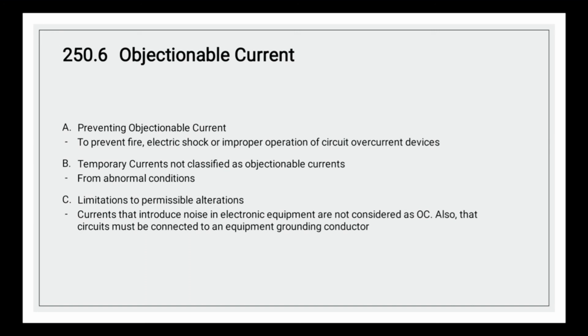Okay, why is temporary current not classified as objectionable current? Because these temporary currents come from abnormal conditions such as ground faults. Okay, regarding the limitation of objectionable current, if the current introduces noise in electronic equipment, that current is also not considered objectionable current. Therefore, this circuit must be connected to an equipment grounding conductor.